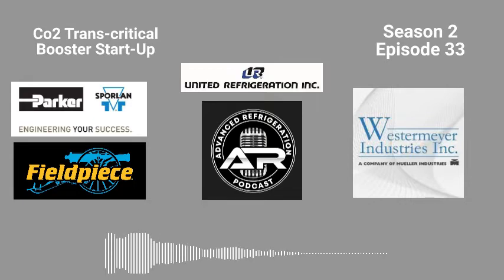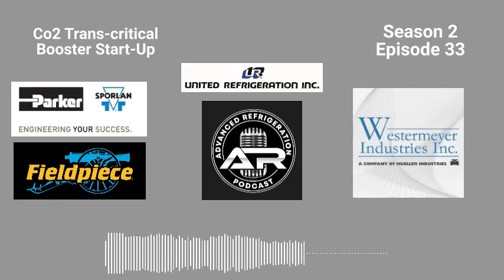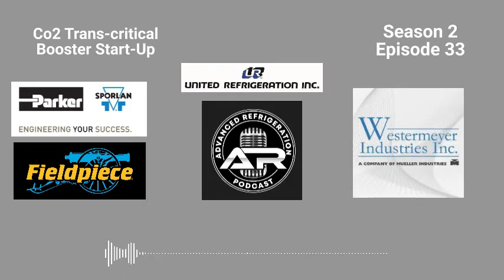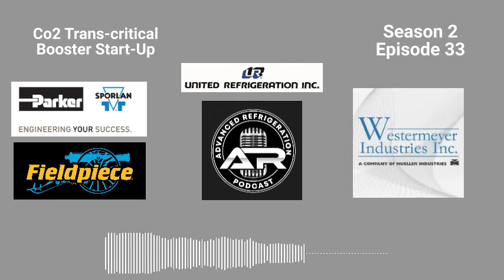All the transducers read. That's why you want to check those under pressure, because the biggest thing on startup is flood outs, because you have temp sensors crossed, transducers not reading, case controllers messed up. So you want to get everything online, everything ready to go before you do anything. And then most importantly, turn the drain heaters on for the walk-ins. I don't know how many construction jobs this gets missed on, because the electricians mess something up and it gets missed, and then we ice up drain lines. So you want to make sure those are on before I start.